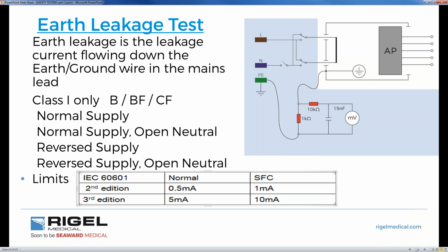So earth leakage is a fairly vital measurement. We're measuring any of the leakage from capacitive coupling on any of the stray capacitance within the medical device. This is going to be a familiar drawing. This would be the chassis of the medical device. This is our live and our neutral, and this is our applied parts, which should be totally isolated, or opto-isolated, from any of the electronics or conductors from the mains in.